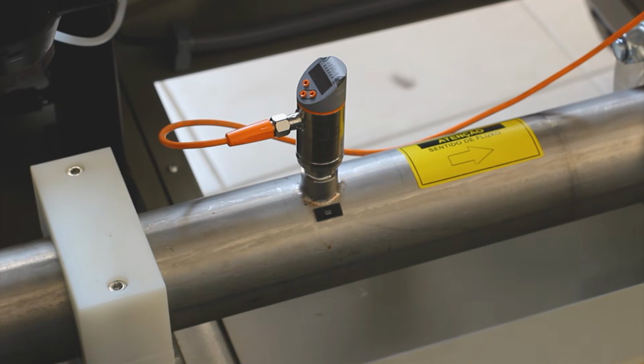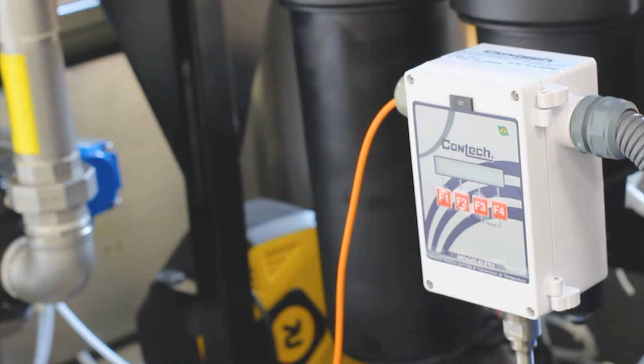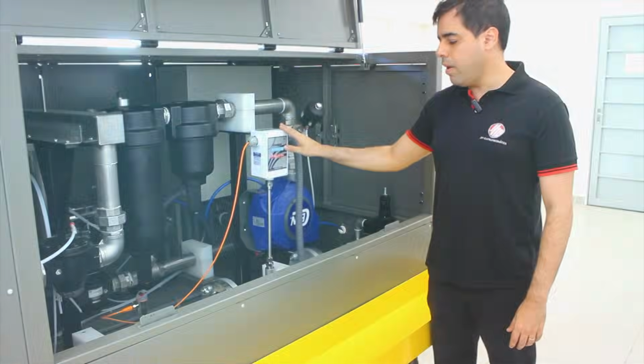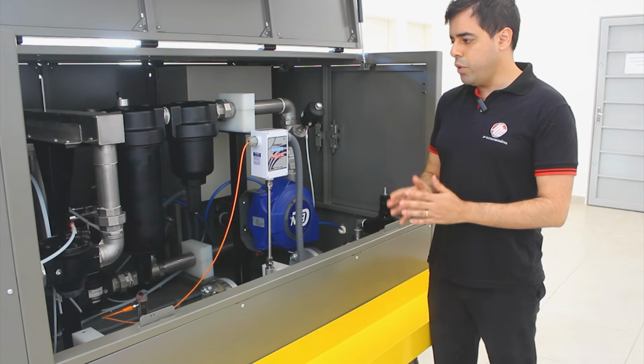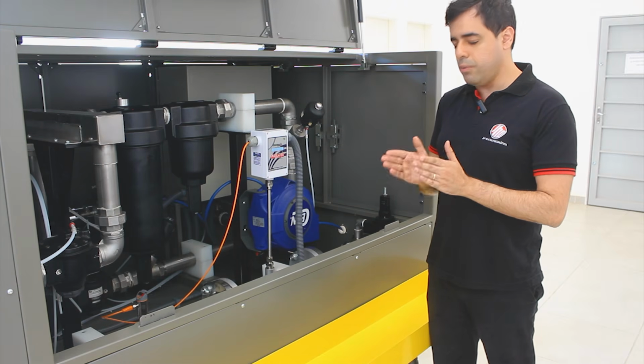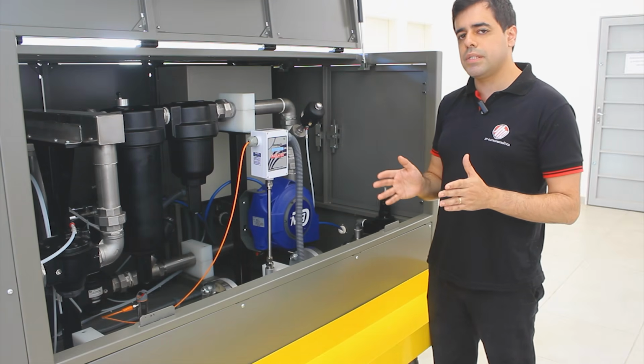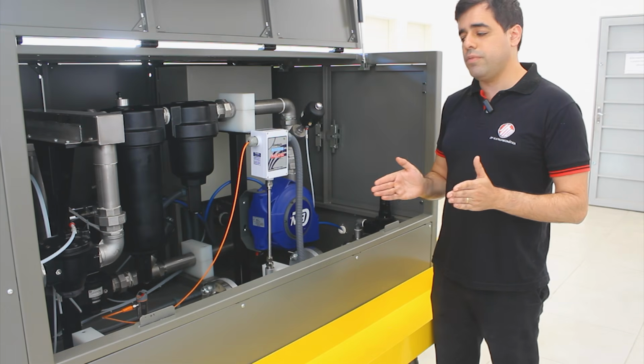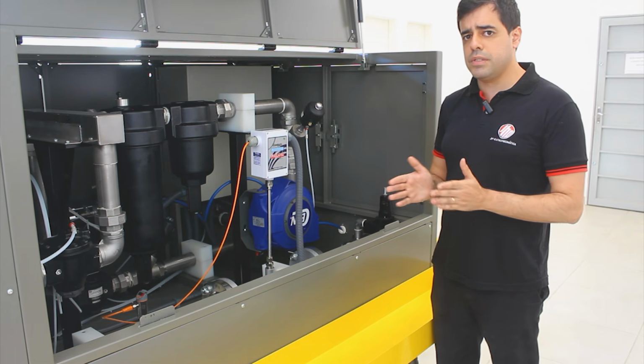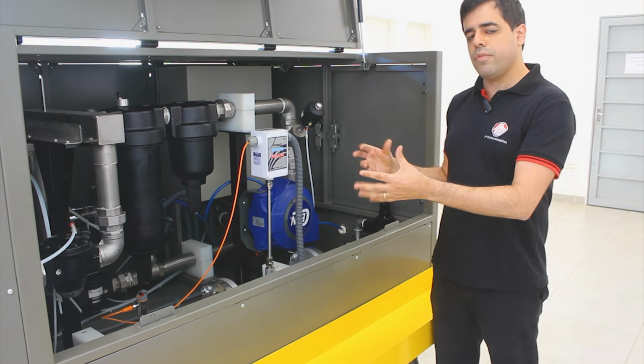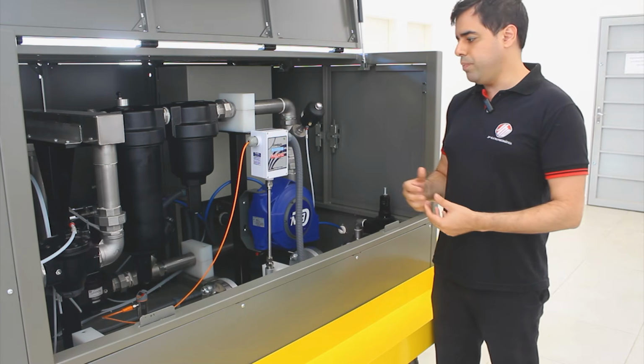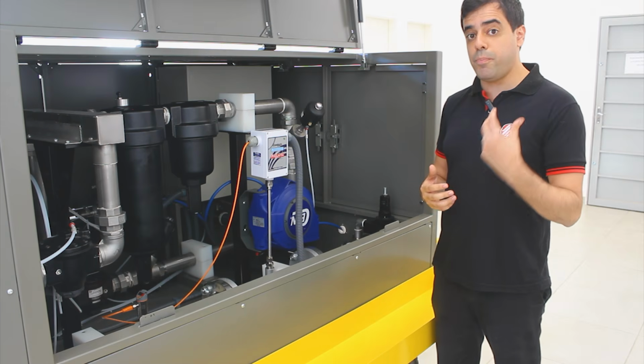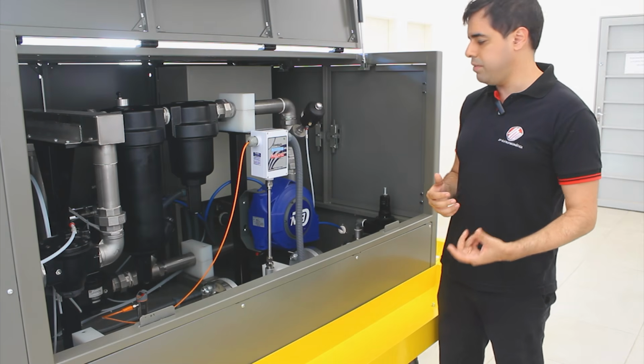We have two mass flow meters that monitor themselves, with a calibrated difference between their measurements. Whenever there's a difference, we can affirm that one of them is uncalibrated, so the calibration is gonna be predictive from now on, not preventive.